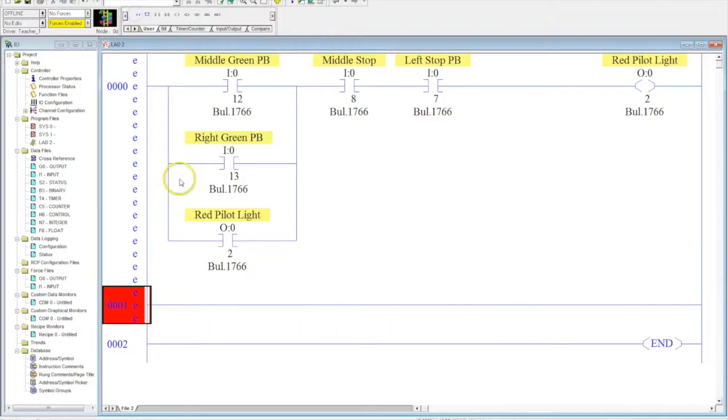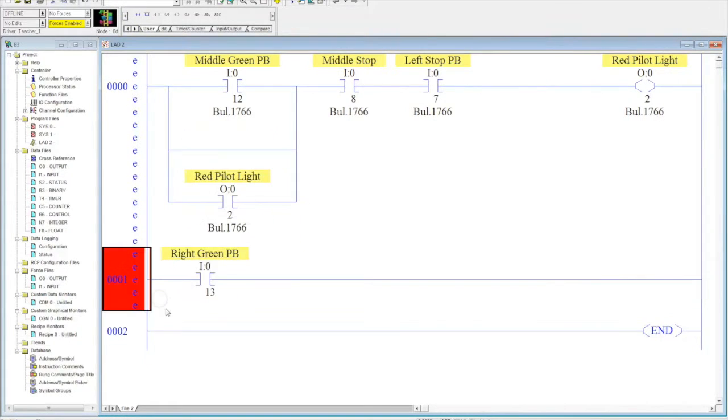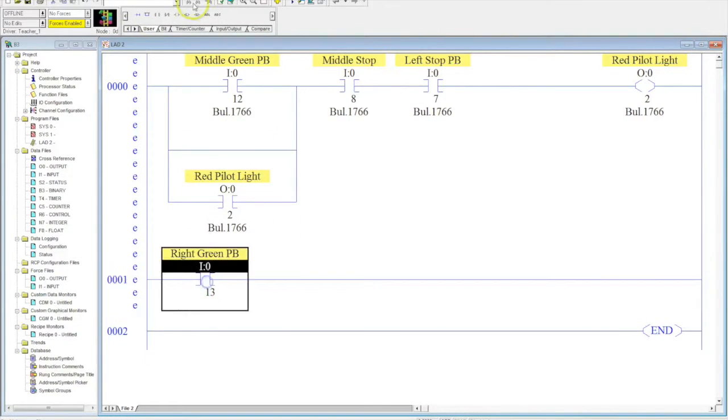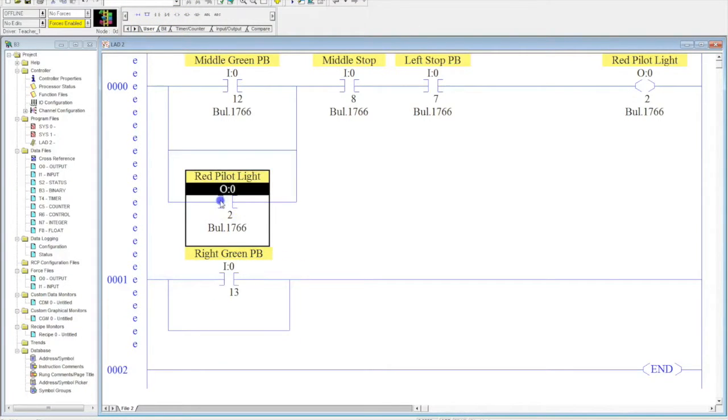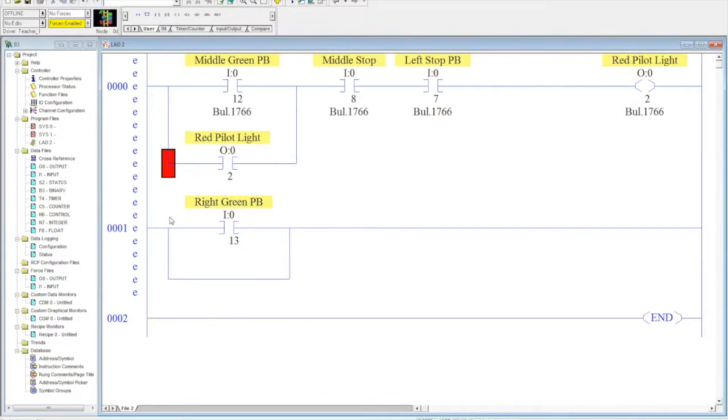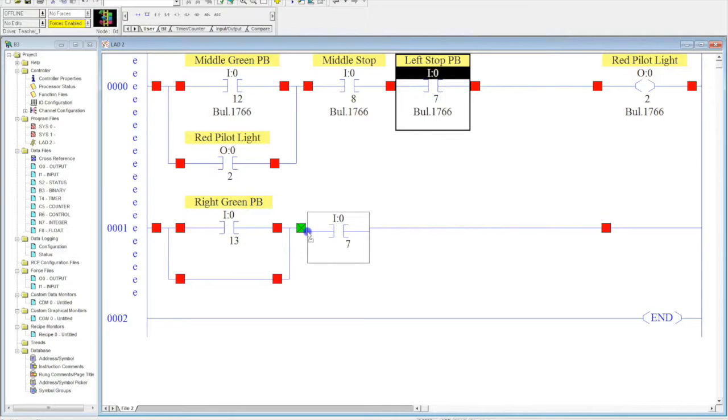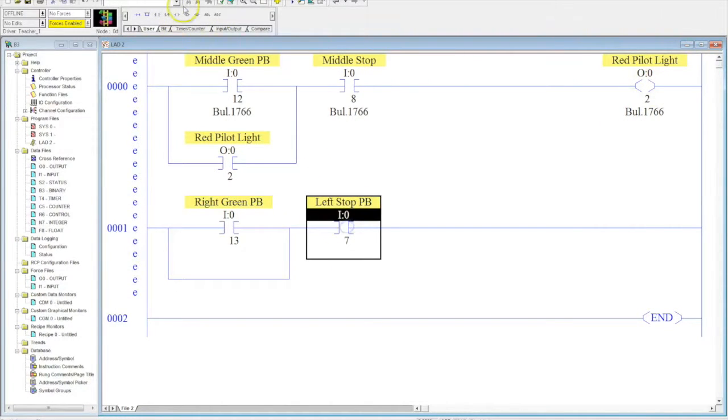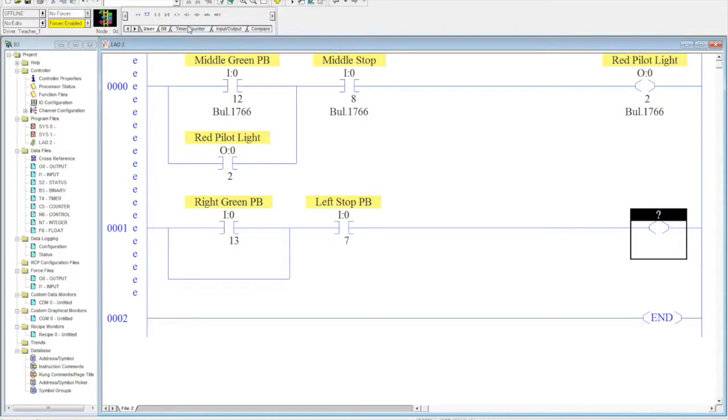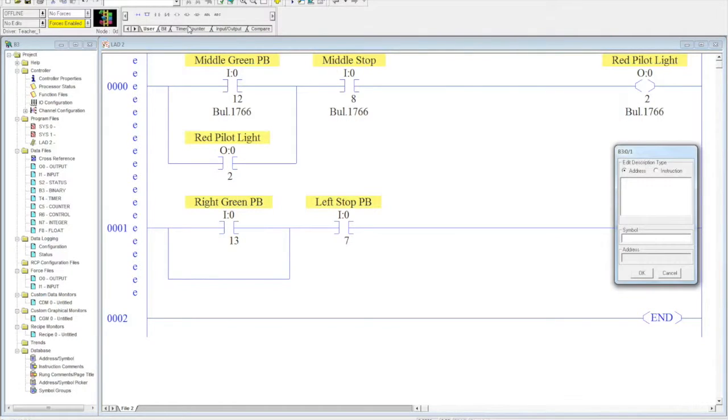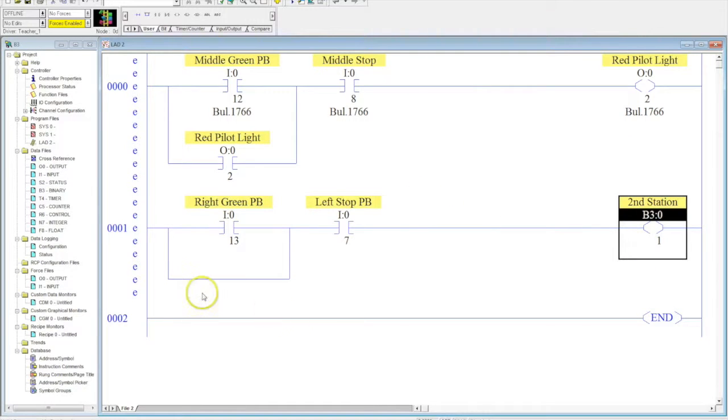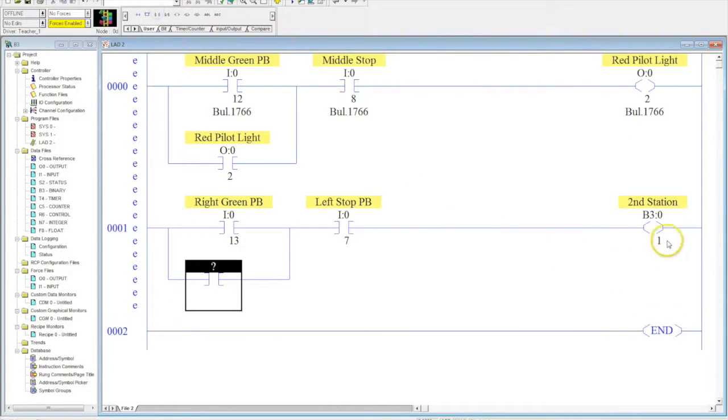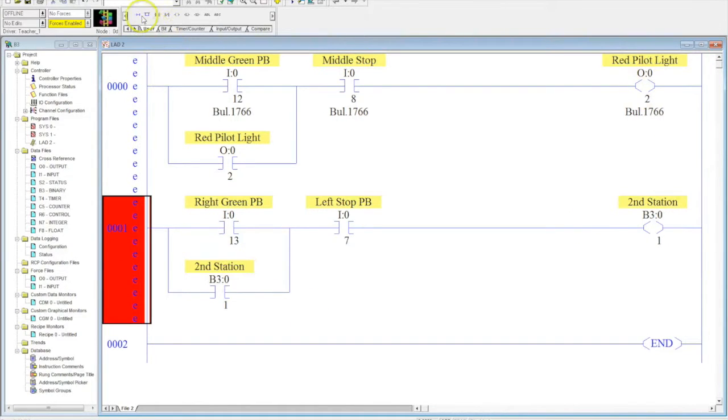This is what I'm going to do. I'm going to add another rung. And I'm going to drag my second start button down to here and drop memory around it. I'm going to bring this memory back up here, basically getting rid of that third branch there. I'm going to grab my second stop button, drag it down here. Then I'm going to put an output on here. And this is going to be my B3. So B3, 0.1. And I'm going to make this my second station. You can name it anything you want. Now I need memory around this from my B3. Again, it acts just like an output. So this will work perfect.